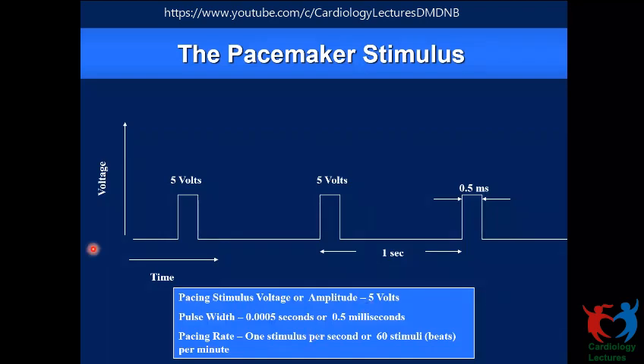And then when we are stimulating with this kind of system, the pacing system allows you, as you definitely know, to program an output in terms of voltage, and it also allows you to program a pulse duration. These two are related, which we will discuss in greater detail. So in this system, we have programmed an output of 5 volts, and we decide to, let's say, pace at a rate of 60 beats per minute, which means we want to pace the heart every 1 second. When we convert seconds into milliseconds, it's 1000 milliseconds. So we deliver a 5 volt output at a duration of 0.5 millisecond, which is 1/2 of 1,000th of a second. We start the pulse, and 0.5 milliseconds later, we switch off that pulse.